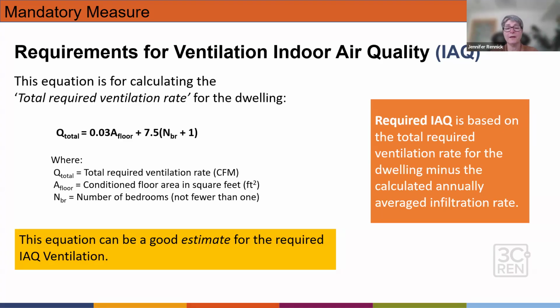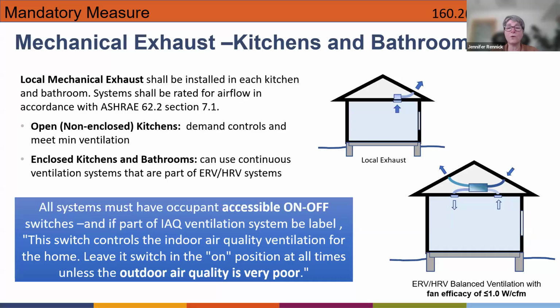And that separate system can be a balanced system, it can be an exhaust only system, or a supply only system. And that balanced system can have heat recovery or energy recovery. And also, we are going to have mechanical exhaust in the kitchens and bathrooms. So what we see a lot in current practice is to have that local required exhaust from your bathroom, exhaust only, run continuously and double as your fan system for bringing in your outside air.